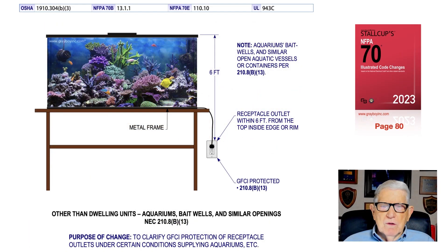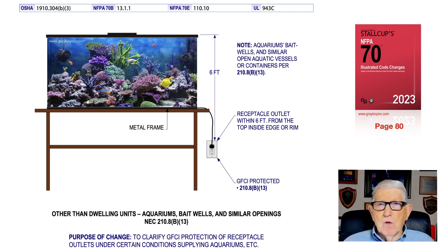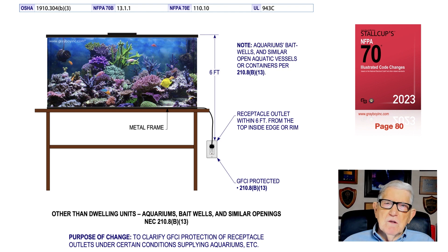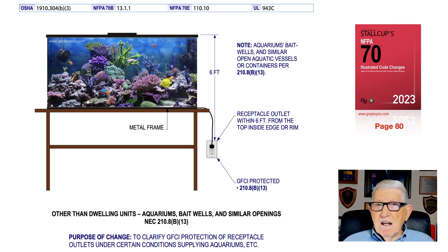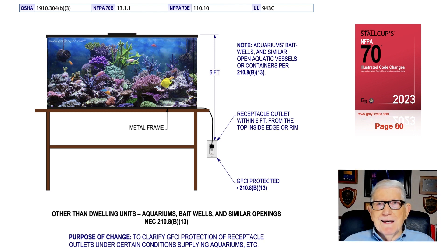This illustration deals with other than dwelling units — aquariums, bait wells, and similar openings declared as such by the authority having jurisdiction in accordance with 90.4. Aquariums, bait wells, and similar open-type vessels are outlined in 210.8 B13. If a receptacle is located within six feet of the inside edge of the rim, GFCI protection is required in accordance with 210.8 B13, found on page 80 of the NEC.